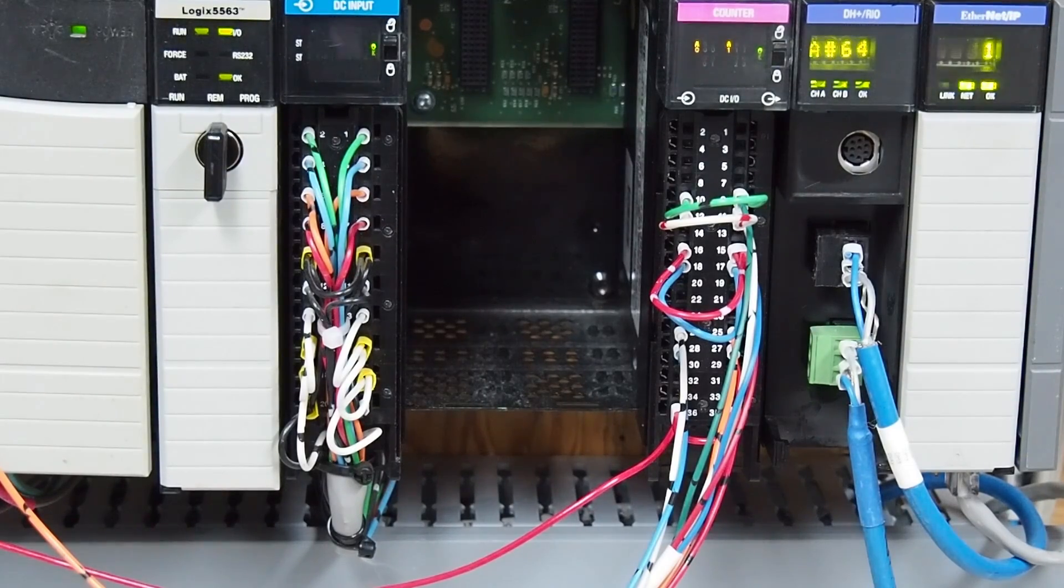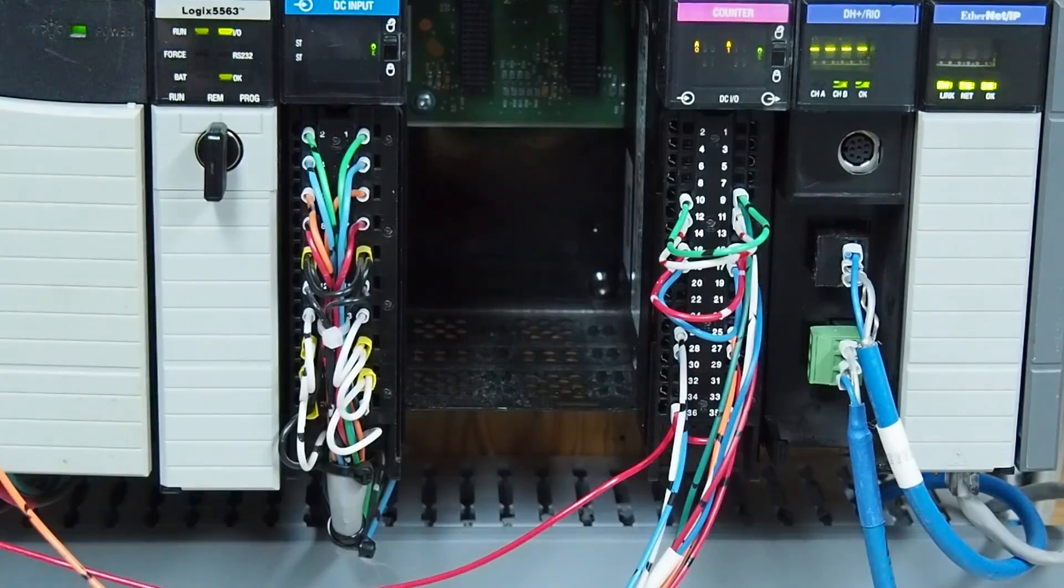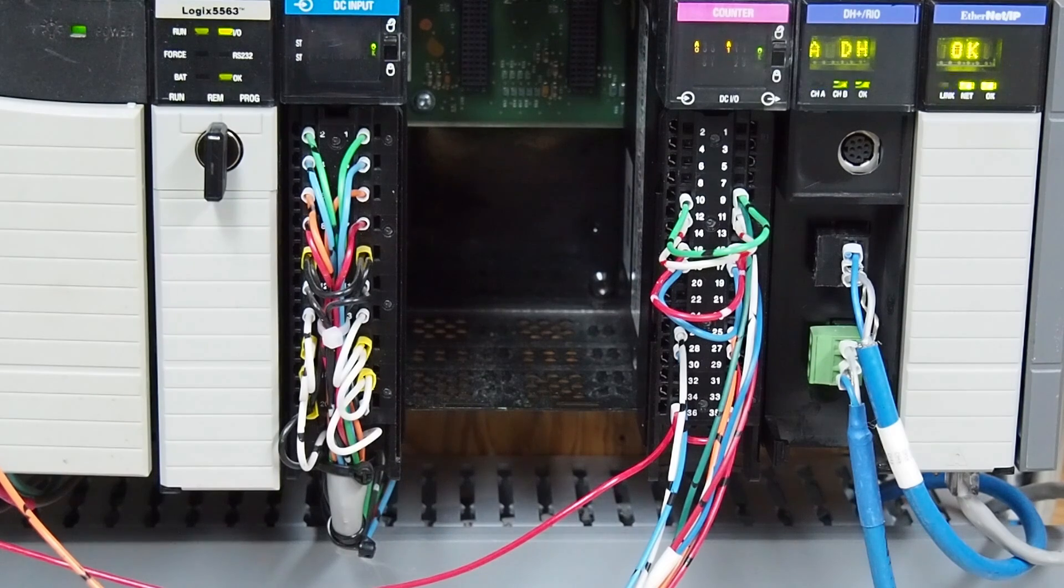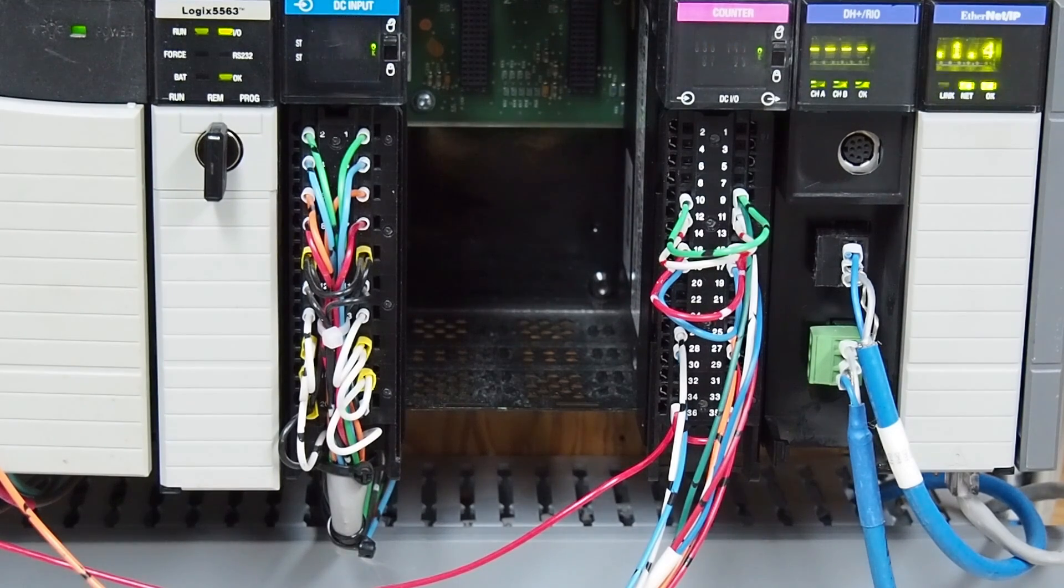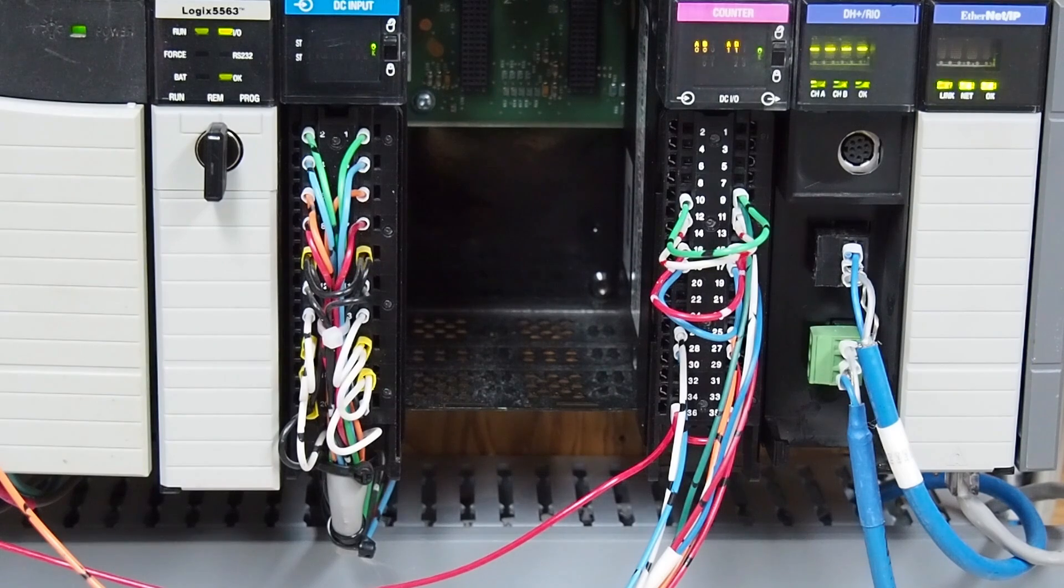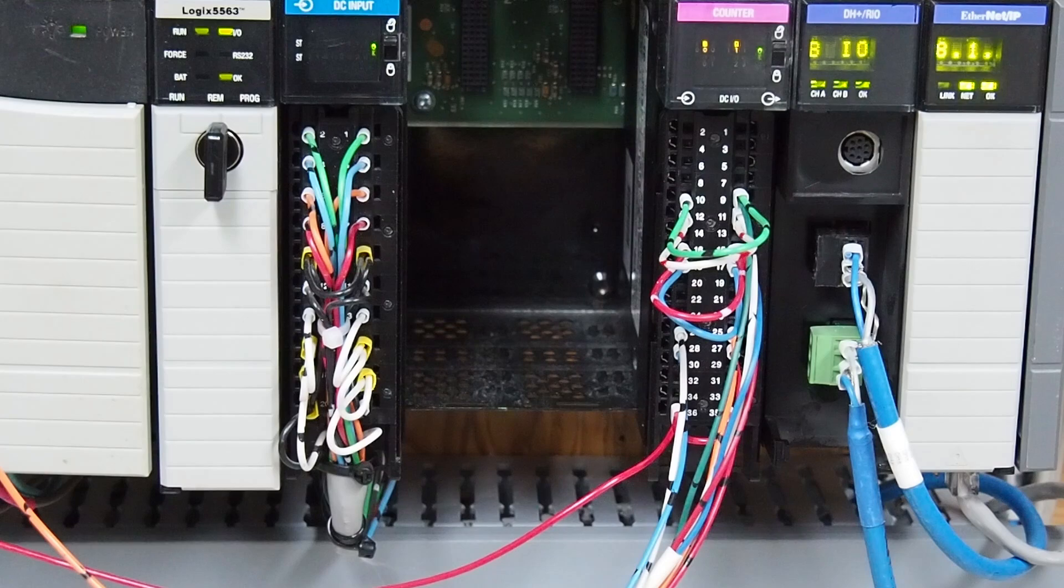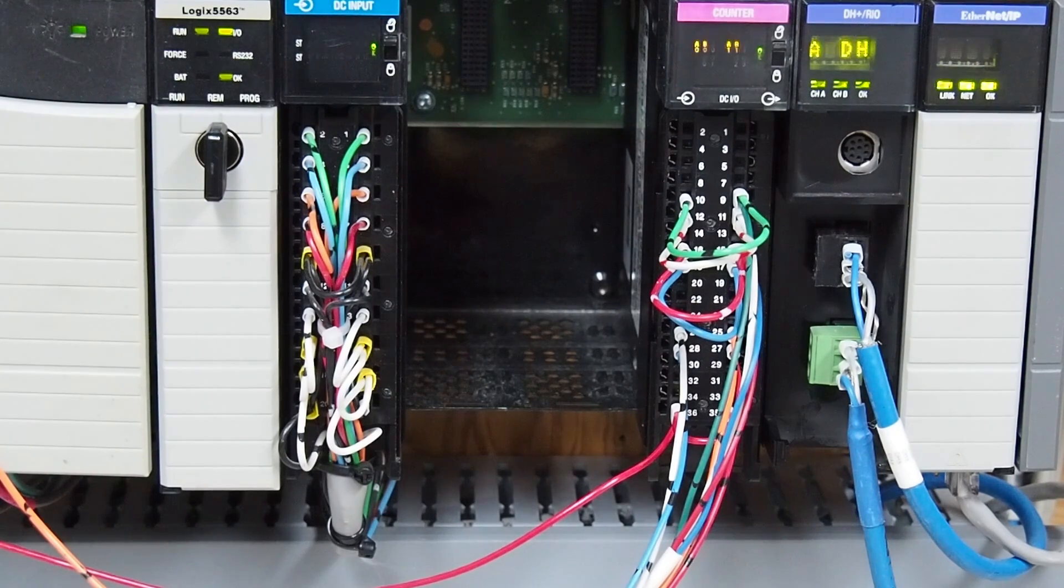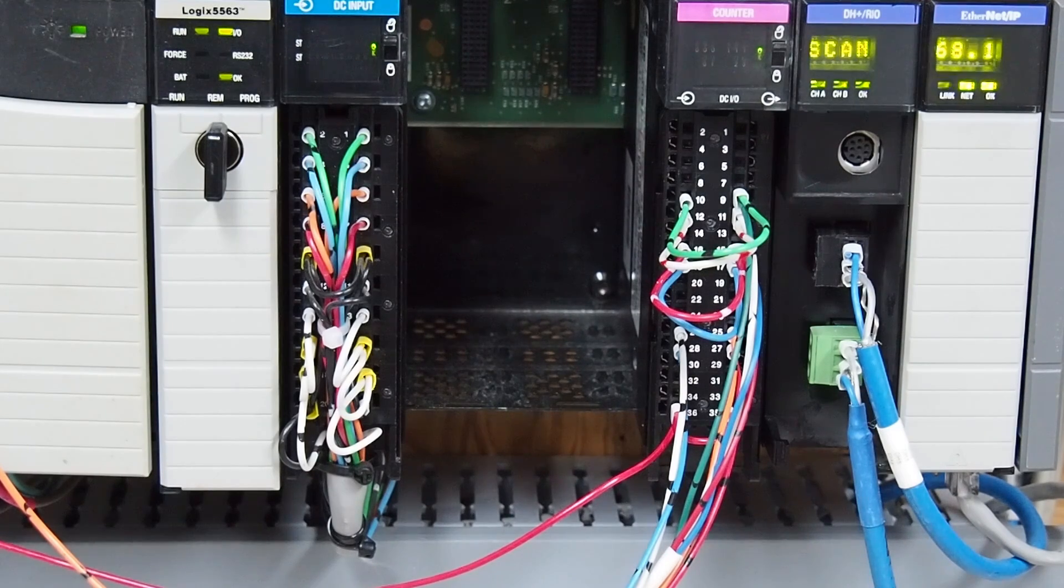Okay, we're back. So as you can see, we have the card in the chassis. And you can see a couple of lights on on the chassis. Now those are the encoder inputs. And as I slowly rotate this shaft, this is a 250 pulse per revolution encoder. You can see the indicating lights showing that you've got your input for channels A and B on both.